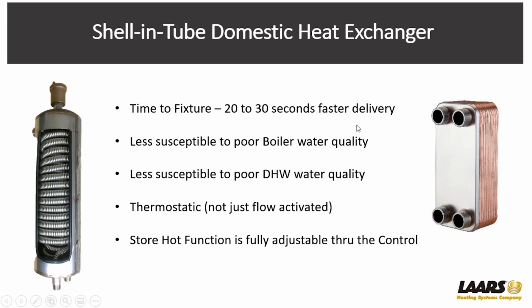And especially if a contractor is putting in a whole new system. So you're pulling out a boiler and maybe they had a tank type water heater. Well, that tank type water heater had stored energy. What I mean by that is if you set it at 120, 125, or 130, it always has 125 or 130 hot water in the tank. As soon as you turn on a faucet, you're delivering that hot water. With a plate type, you're not. So you have a lot of customers complaining about, especially if they had a tank type water heater and now they go to a wall hung or a combi type boiler, it takes time to get that hot water to my fixture. With the shell and tube design, we're always in tank charge mode.